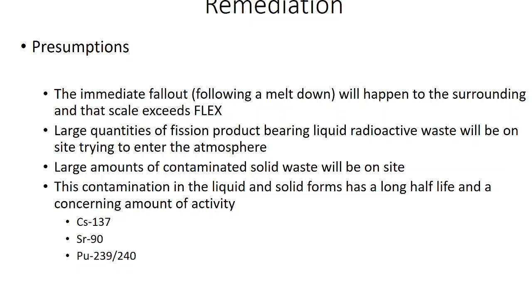We can possibly deal with those radionuclides later by collecting runoff in storm sewers and trying to filter them out mechanically or through ion exchange. But at the plant, we will have a large amount of liquid radioactive waste. We'll have a waste processing facility, but those only work so fast, and chances are good we're going to be generating this contaminated radioactive liquid faster than we can store it in a tank. So we are going to have to figure out something to do quickly to deal with that.